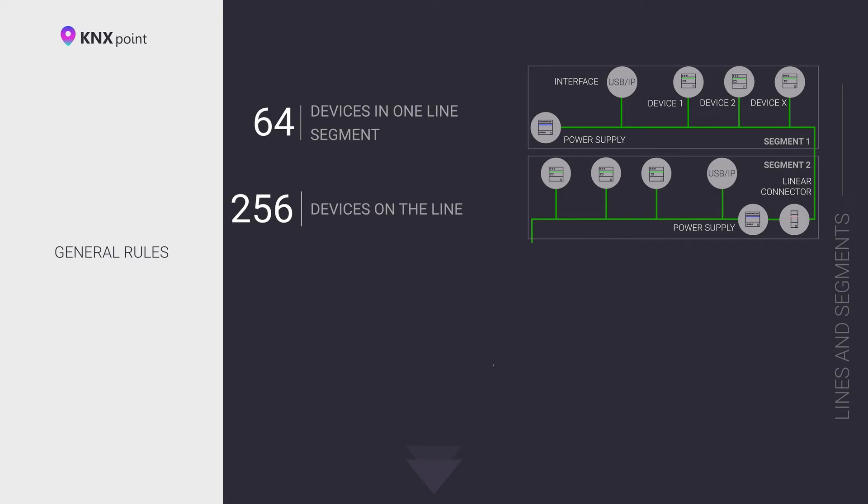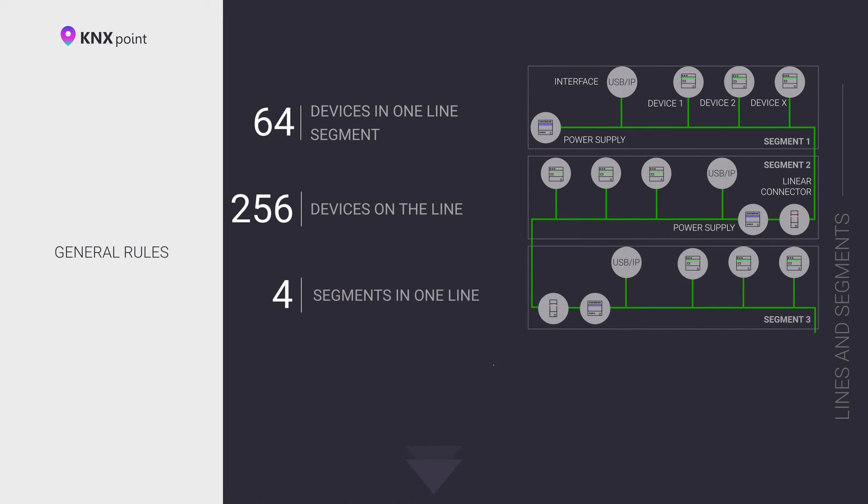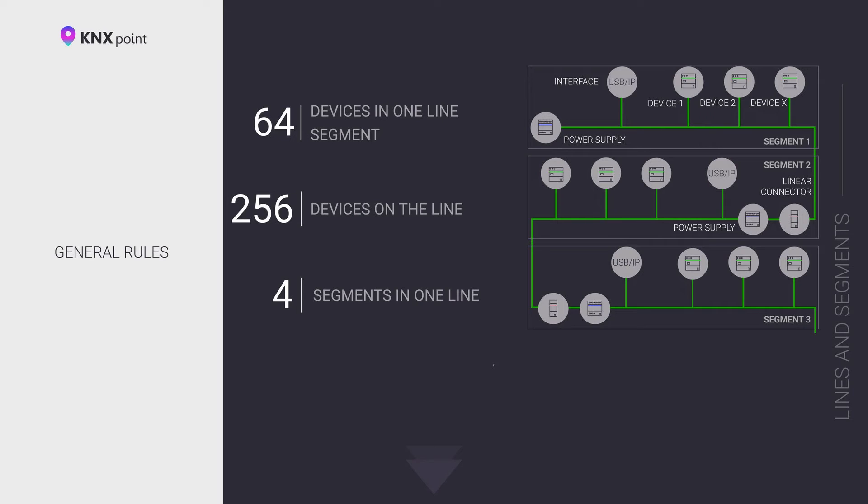Basic rules for KNX bus topology design. The line coupler is used to connect bus segments and lines. A segment is a set of KNX devices physically connected by a KNX bus. Each individual segment of the KNX bus must be powered by a power supply. It is worth choosing a KNX bus power supply with sufficient power to power the devices connected to the KNX bus segment.